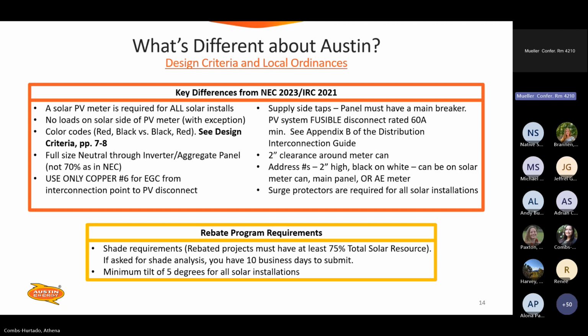If there's supply chain issues and you can't find it, at the bottom of that page, there's a little directive on how to get approved for a non-approved meter can if there are supply issues, but be aware of that. That's very critical. So there's no loads on the solar side of the PV meter. There are some exceptions to that, like the battery, for example. So if you've got a system design that requires the battery to be, say, DC coupled, or for some other reason on the solar side of the PV meter, that would be acceptable. But you don't want to be running house loads through the PV meter.